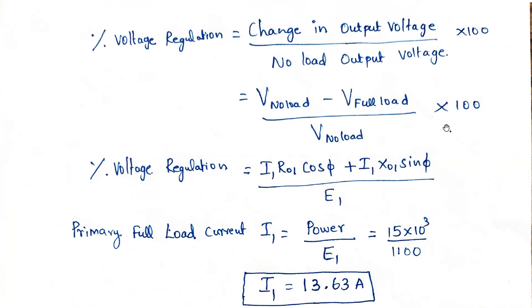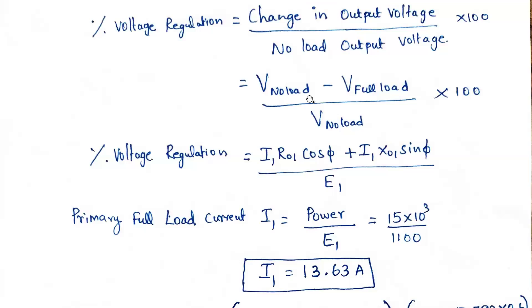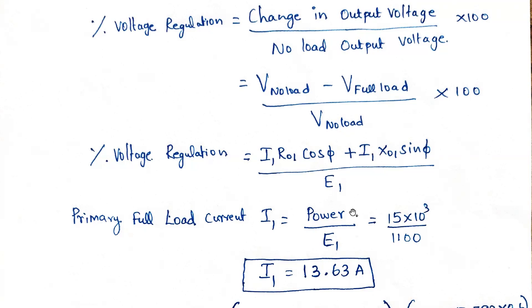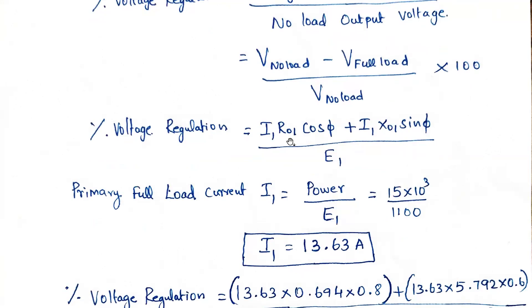Voltage regulation equals no-load voltage minus full-load voltage divided by no-load voltage, into 100. The formula becomes: VR = (I₁R₀₁ cos φ + I₁X₀₁ sin φ) / E₁ × 100. Here we are taking values with respect to the primary side. The same answer will come if taken with respect to secondary as well.